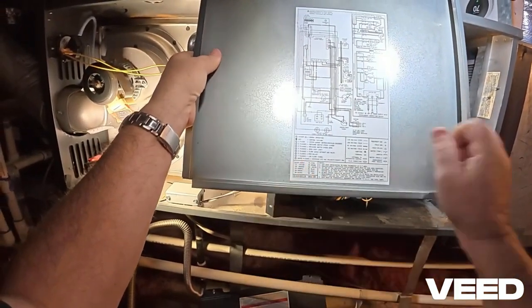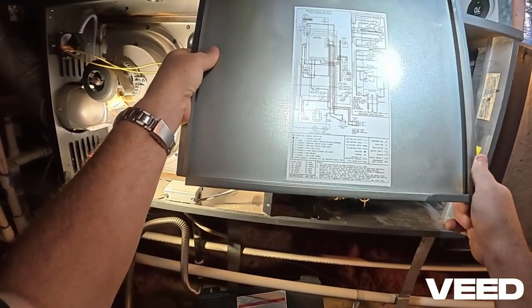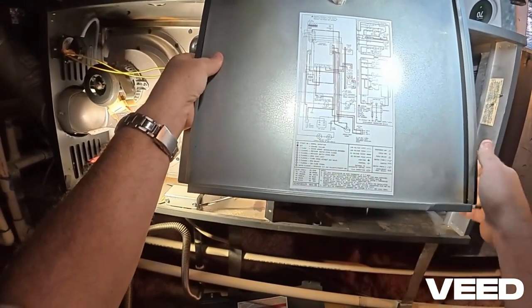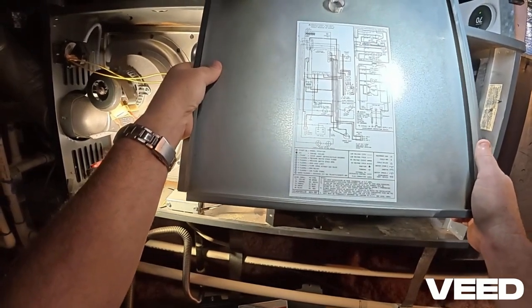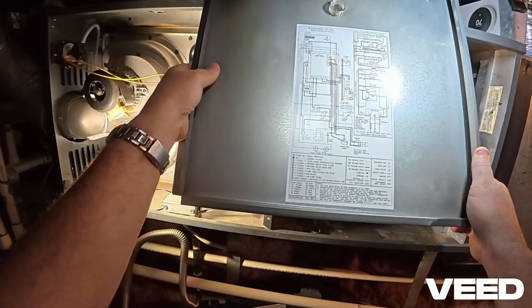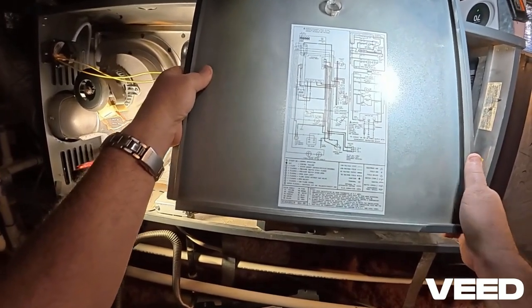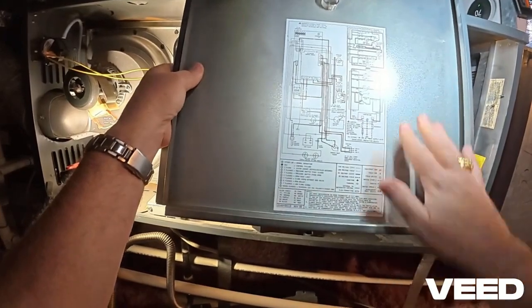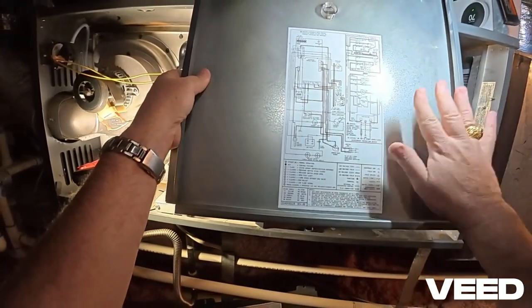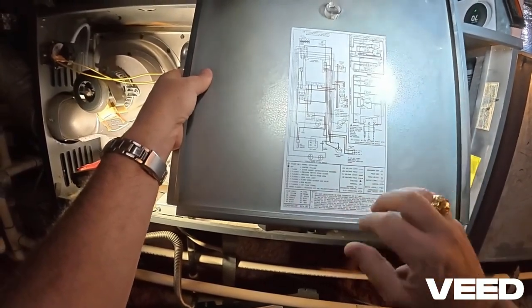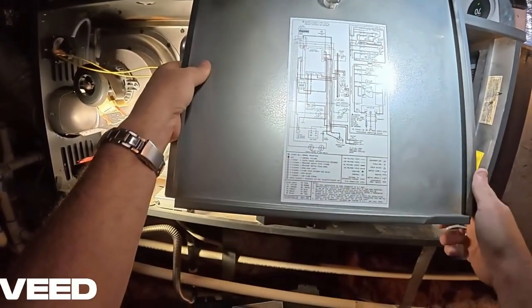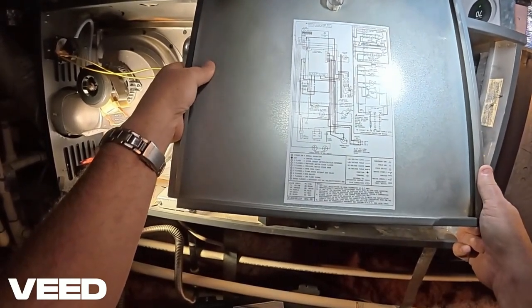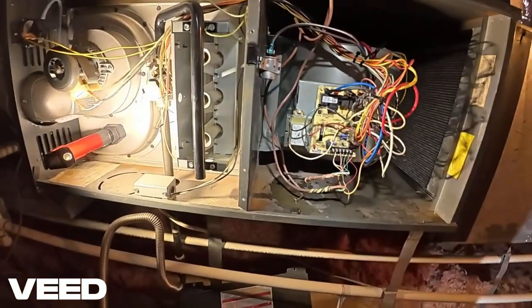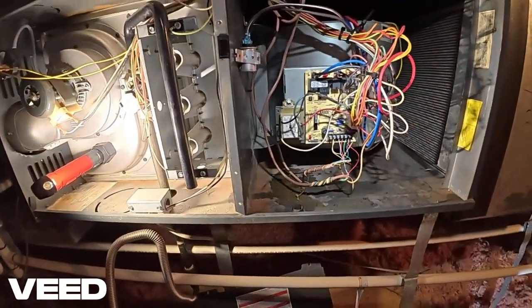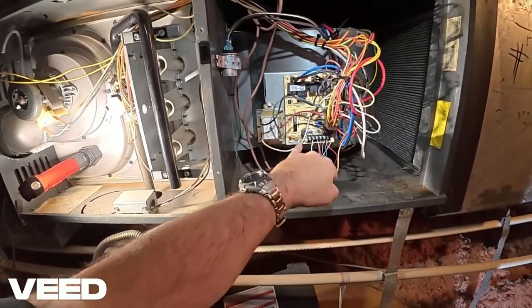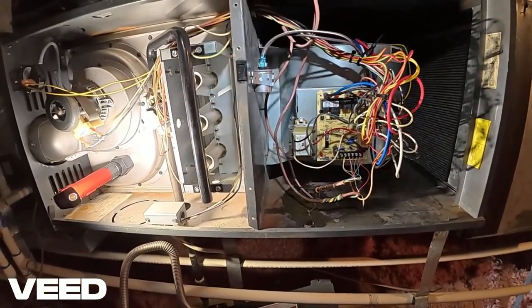The last one here is rapid flashes, reverse polarity, verify ground. So that, I personally haven't seen that one, but I suppose it's possible. And again, it could be a transformer issue, possibly control board as well. But again, there's one of these on every system. Typically it's on the panel. Your manufacturer will likely be different, but that hopefully gives you some indicators and pointers as to what the flashes mean and where you find the lights and what it might be pointing to.